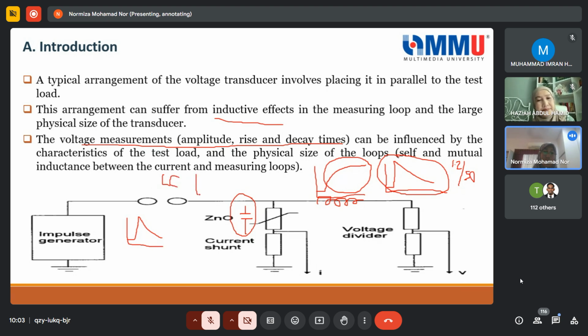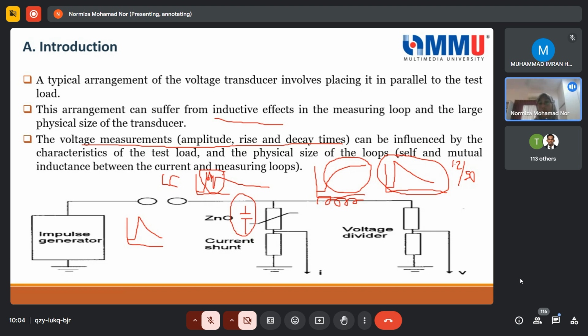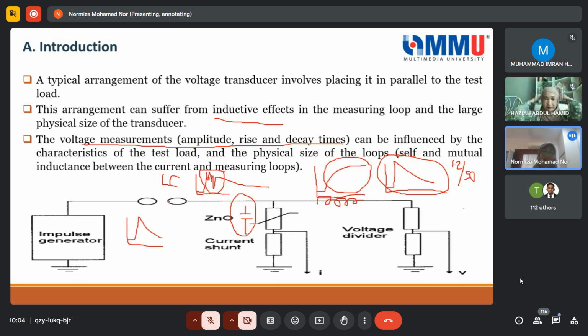So when you have L and C, what happened to this smooth, fast response time? It will be like this. You may have oscillation here, and then it goes like this. Of course, you do not want this initial oscillation on the voltage reading, because how are you going to put it in your manufacturing data sheet? If the buyer sees this, of course they are not convinced with the equipment that you are measuring. So that's why the high voltage test engineer has to make sure that this is calibrated, and at the same time the measuring device should be adequately accurate, because they have some tolerance as well, like 10%, 30% and so on, and should represent the real results that impinge on the test load.